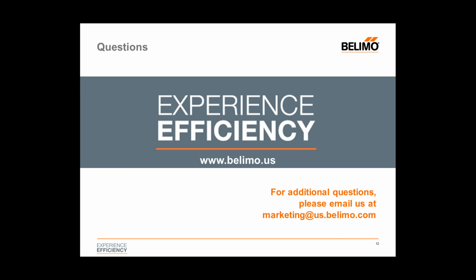Can you change the BTU calculation to adjust for changes in specific heat and gravity when brines are used? The units can be changed for BTU, so it can be changed to tons or kilowatt hours and so forth. But the energy valve itself is probably not the best application for brine. So what I would suggest there is contact either DSM or contact me directly, and we can work through that application to get you the best information and the best result of what you're looking to do within your application.